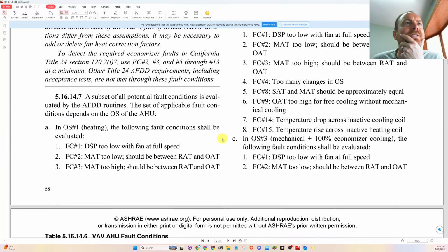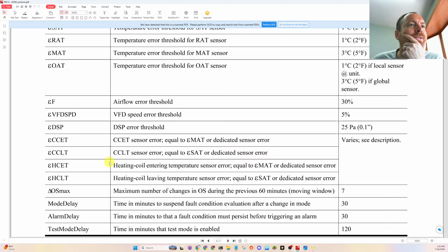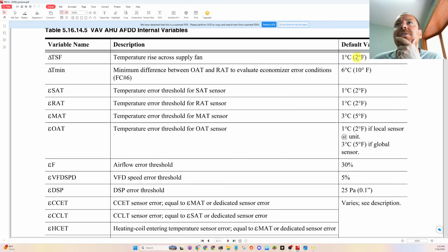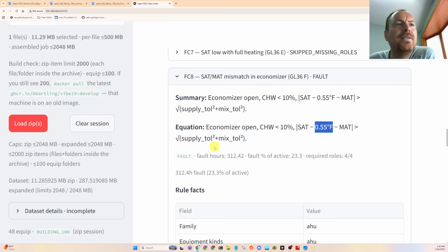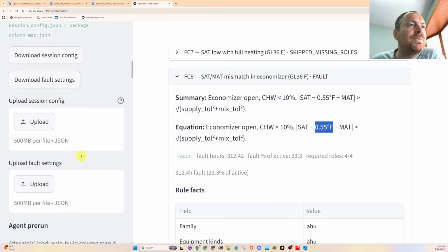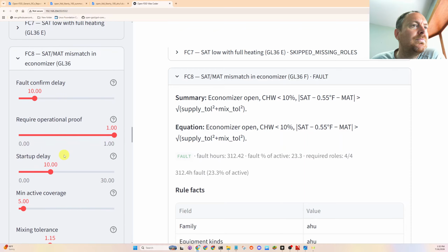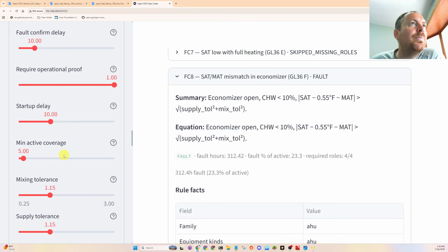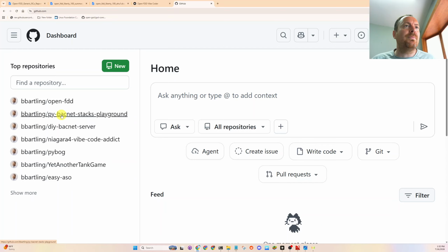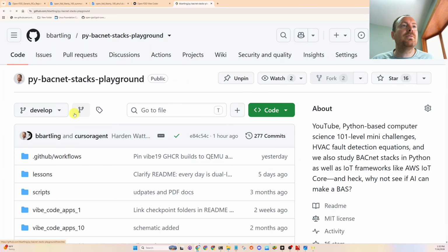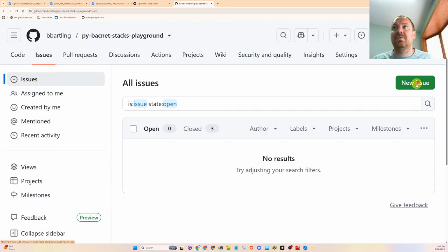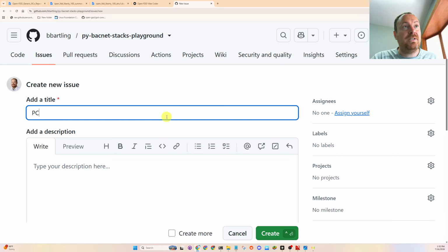I just wanted to validate that this parameter for fan heat, temperature rise across the supply fan, is 2 degrees Fahrenheit. That seems more correct. 1 degree C, 2 degrees Fahrenheit. And then for here, we are hard-coded as 0.55. But this might be an adjustable parameter. Let's just look. Let's make this an adjustable parameter and default it to what Guideline 36 recommends. I don't think it'll make a huge change here, but okay, so FC8.